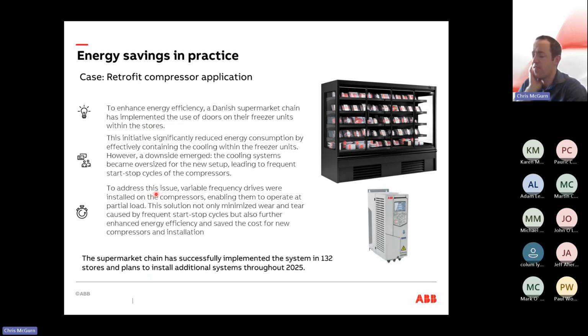So to address that, they added variable speed drives to the compressors, enabling them to operate at partial loads and to only switch on whenever they're actually required. That improved efficiency, and it also minimized wear and tear on the compressors themselves by preventing the start-stop cycles that could cause damage over time. The supermarket chain implemented the system in 132 stores and plans to install an additional system throughout 2025. So that was a good example of how VSDs can improve systems.